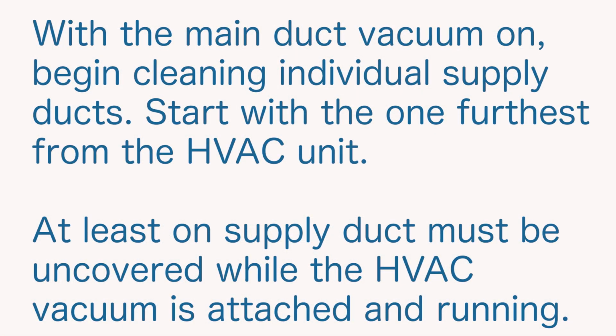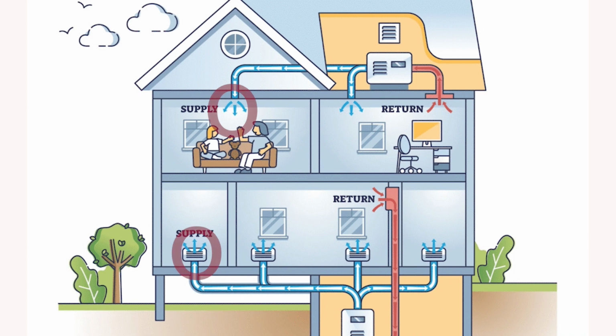With the main vacuum on, begin to clean the air ducts. Start with the duct that's furthest away from the HVAC unit. At least one supply duct must be uncovered while the main HVAC vacuum is running. Start cleaning the supply vents, starting with the one furthest away from the HVAC unit that you're working on. These can be found by following the ducts or going to the opposite end of the house.